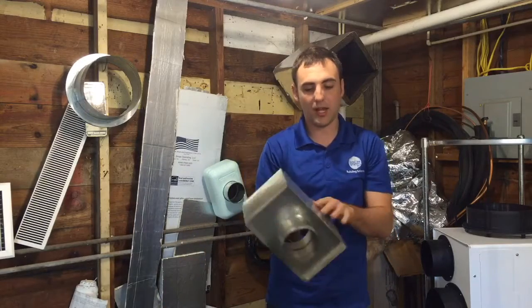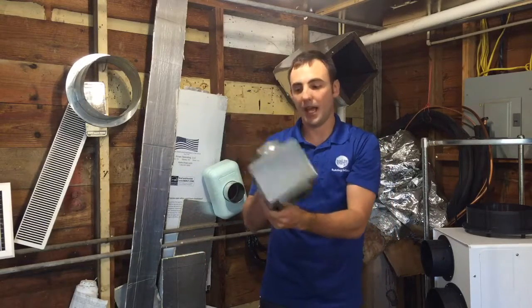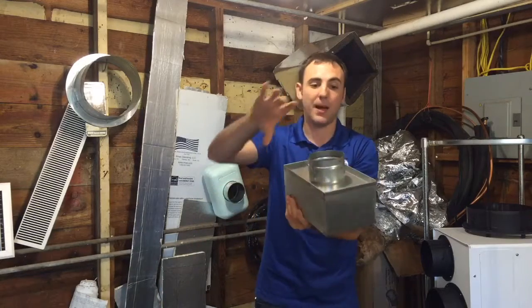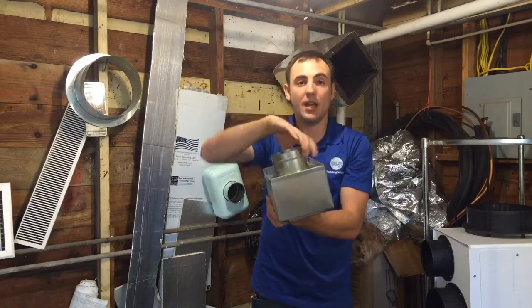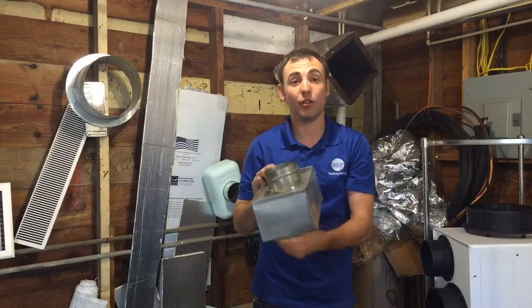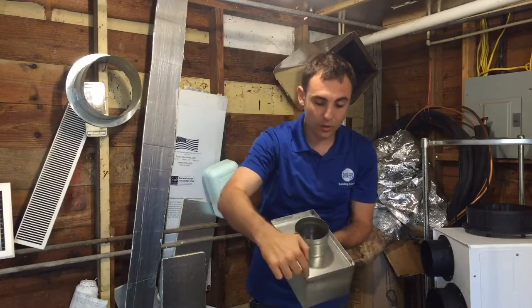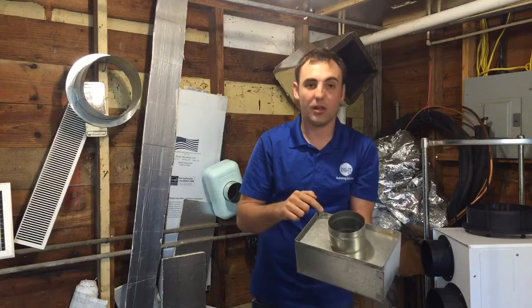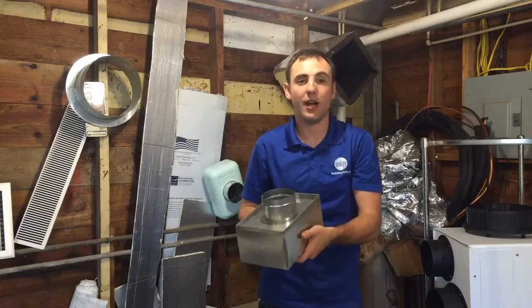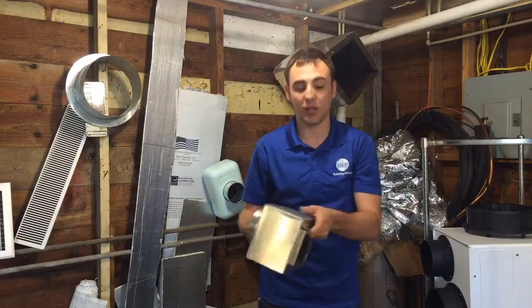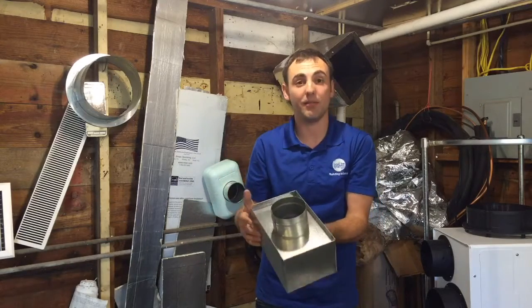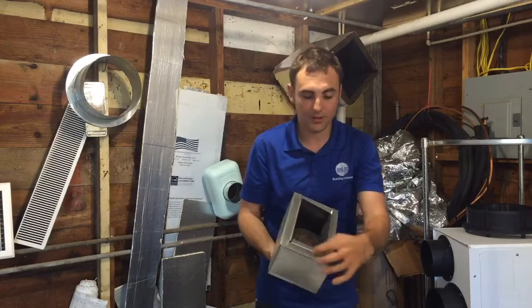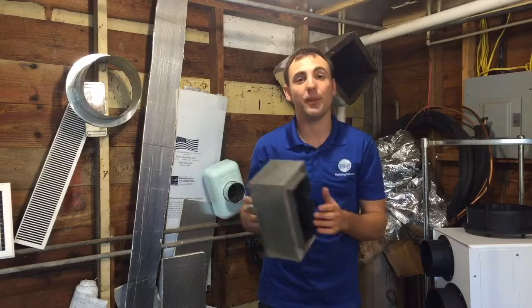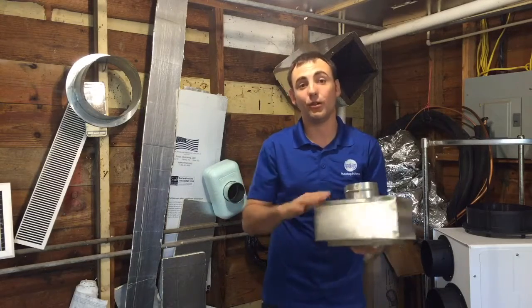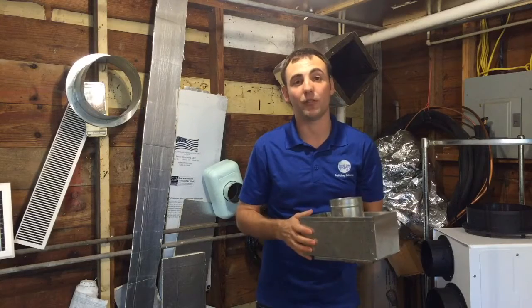One other thing to mention, here is a supply bucket, and typically the flex duct or even metal pipe will connect to the back side of this. And we were talking about duct leakage earlier, and each one of these corners here leaks a little bit of air. If you have 20 of these in your house, it can really add up the amount of air leakage that comes from just the back side of this bucket. Not to mention the front sides here have little slits, and this thing leaks air all over the place, and the HVAC contractor needs to know that those things can be sealed up to really improve the efficiency.